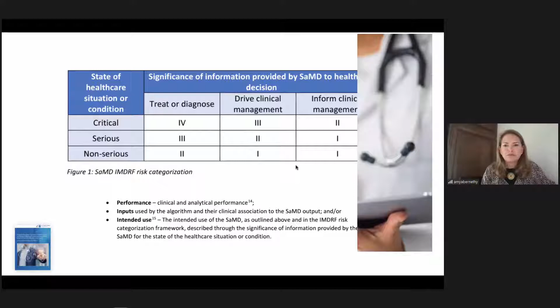And in 2014, this was the SaMD risk categorization approach, acknowledging that the types of software-based medical devices would be used in a variety of contexts, and those contexts could be classified into categories of risk. The risk categories that you see here, 4 categories of risk, are classified as 1 through 4. And practically speaking, the way that we allocate that risk is by understanding if the state in which the SaMD product is to be used is non-serious, serious, or critical, and that the kind of task that that product was going to be put in place for was to treat or diagnose. There's higher risk tasks, drive clinical management, medium risk tasks, or informing clinical management.